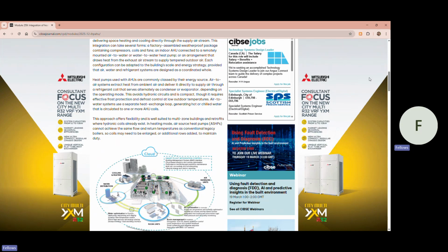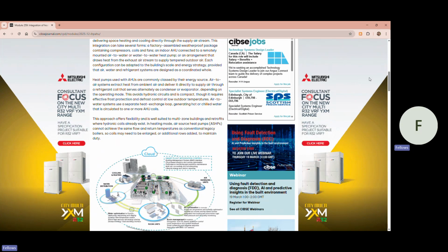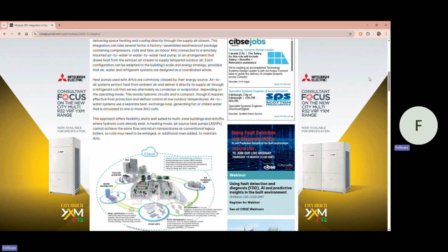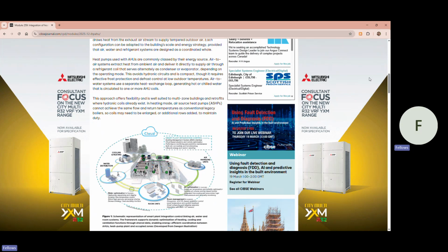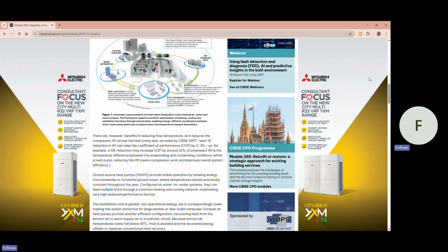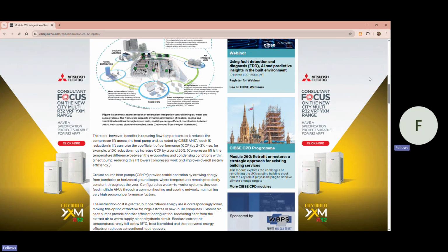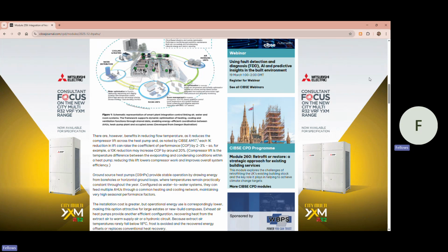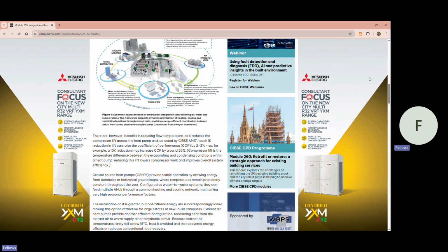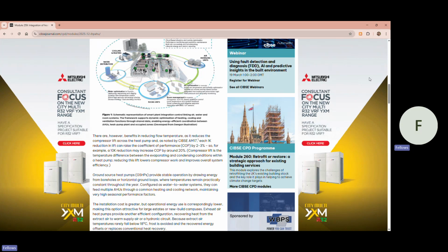In heating mode, air source heat pumps, or ASHPs, cannot achieve the same flow and return temperatures as conventional legacy boilers, so coils may need to be enlarged or additional rows added to maintain duty. There are, however, benefits in reducing flow temperature, as it reduces the compressor lift across the heat pump, and, as noted by CIBSE AM17, each 1K reduction in lift can raise the coefficient of performance, COP, by 2 to 3%. So, for example, a 10K reduction may increase COP by around 20%.